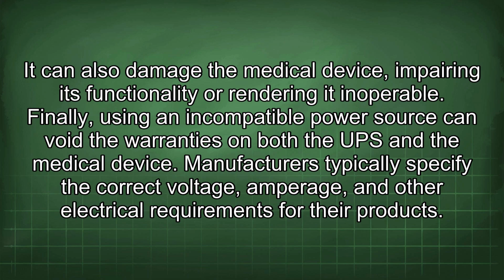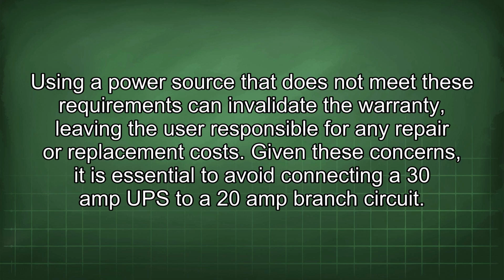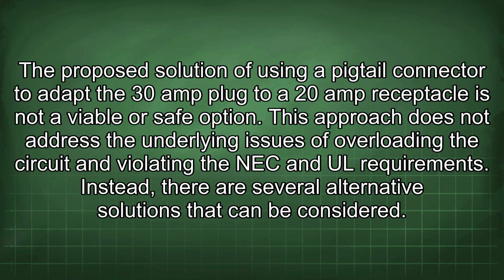Manufacturers typically specify the correct voltage, amperage, and other electrical requirements for their product. Using a power source that does not meet these requirements can invalidate the warranty, leaving the user responsible for any repair or replacement costs. Given these concerns, it is essential to avoid connecting a 30 amp UPS to a 20 amp branch circuit. The proposed solution of using a pigtail connector to adapt the 30 amp plug to a 20 amp receptacle is not a viable or safe option.